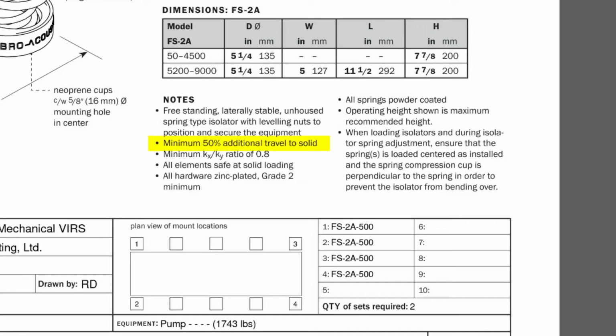This note means that the springs can deflect an additional 50% beyond their rated deflection. In this case, 50% more than 2 inches is 1 inch, so these springs can deflect a total of 3 inches before all the spring coils touch and go solid. It also means they can handle up to an additional 50% more weight than their rated load and still provide isolation. They will not be compressed completely flat unless they've been overloaded with 50% or more additional load.